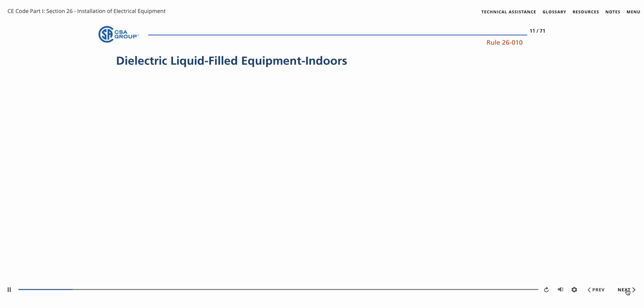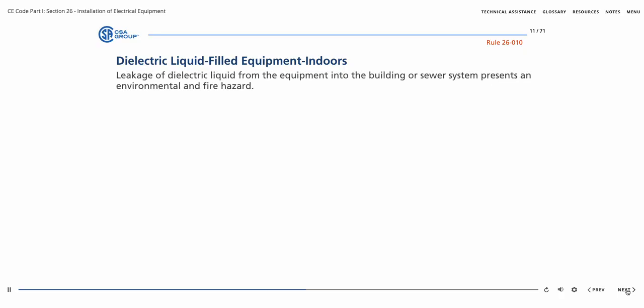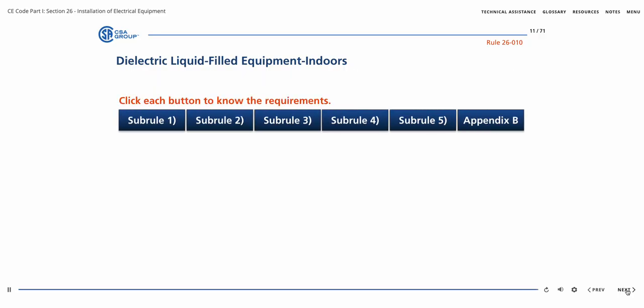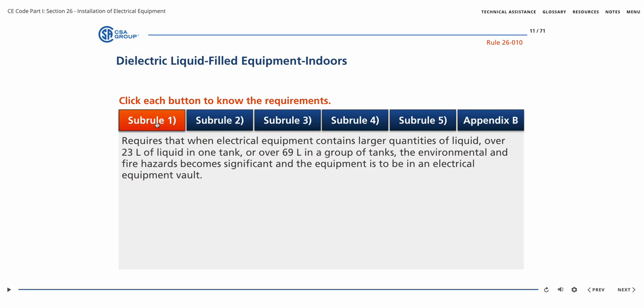In many cases, electrical equipment such as transformers, capacitors, and motor starters are immersed in a dielectric liquid and installed indoors. Leakage of this dielectric liquid from the equipment into the building or sewer system presents an environmental and fire hazard. Subrule 1 requires that when electrical equipment contains larger quantities of liquid, over 23 liters of liquid in one tank, or over 69 liters in a group of tanks, the environmental and fire hazards become significant, and the equipment is to be in an electrical equipment vault.